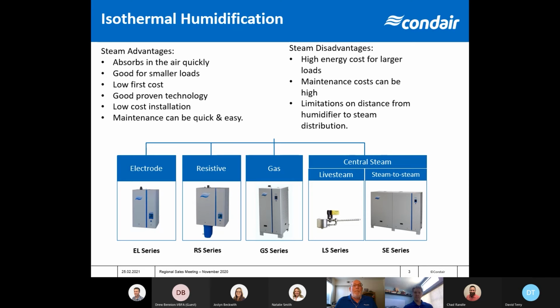So kind of some of the advantages and disadvantages I list above here. The great thing about steam is it absorbs into the air very quickly. On average, probably just a matter of inches. So those can get that steam absorbed really, really fast. As I mentioned, great for smaller loads, good proven technology. These have been around a long time. They can be quick and easy maintenance. As I mentioned with the electrode units and even our resistive units, they work really hard to reduce maintenance for the owner as well. The disadvantages though, high energy costs for larger loads.